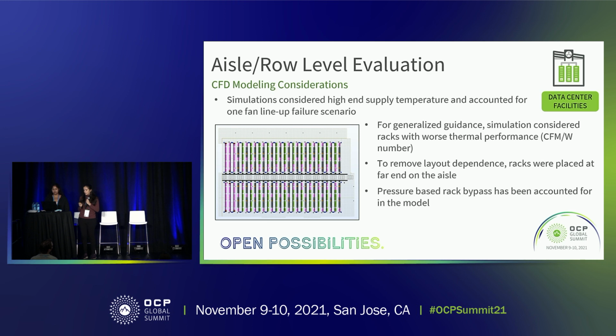And the last was we also took into consideration any effects of pressurization, and whether we have excess airflow through these racks because of the higher pressures that we see in the cold aisle. So by running multiple cases of this, with the assumptions that we have, we are now able to come up with a number for the IT airflow that we are able to support, and use that to assess the cluster plans, to assess what kind of thermal risk we would have if we deploy a certain kind of IT airflow requirement in our aisles. Next, I'll hand it over to Manasa to talk about the rack level considerations.